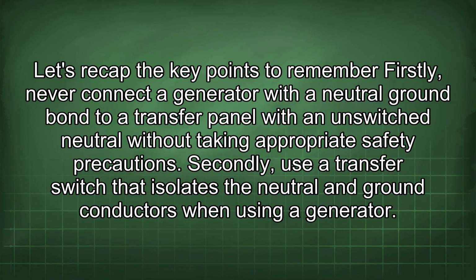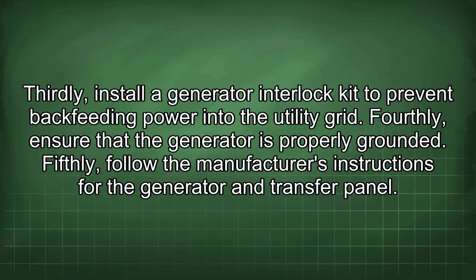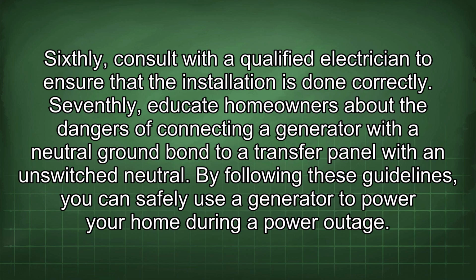Let's recap the key points to remember. Firstly, never connect a generator with a neutral ground bond to a transfer panel with an unswitched neutral without taking appropriate safety precautions. Secondly, use a transfer switch that isolates the neutral and ground conductors when using a generator. Thirdly, install a generator interlock kit to prevent backfeeding power into the utility grid. Fourthly, ensure that the generator is properly grounded. Fifthly, follow the manufacturer's instructions for the generator and transfer panel. Sixthly, consult with a qualified electrician to ensure that the installation is done correctly.